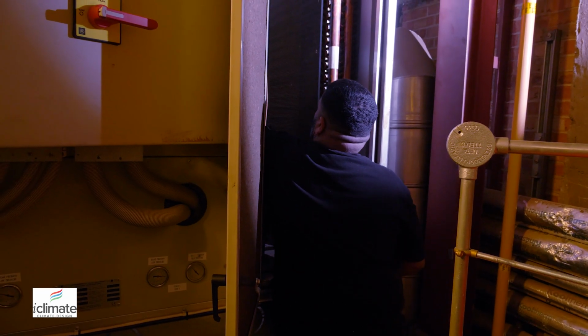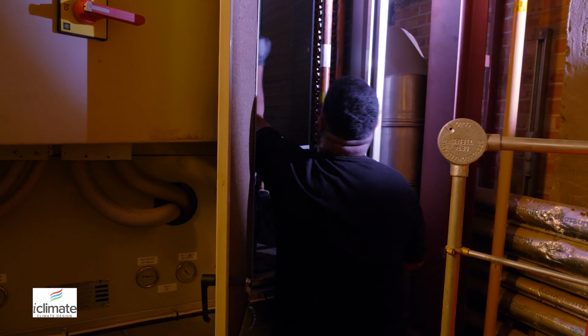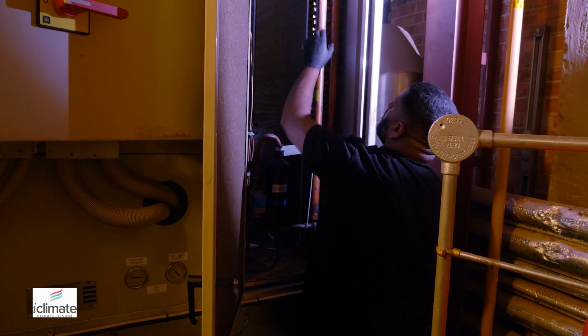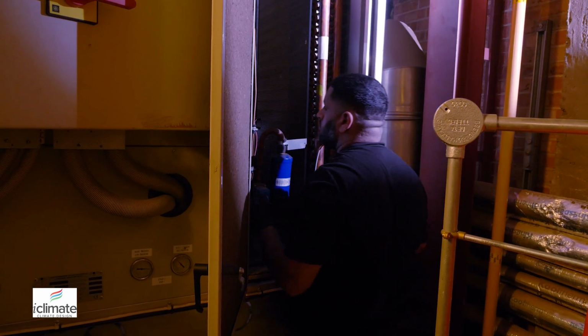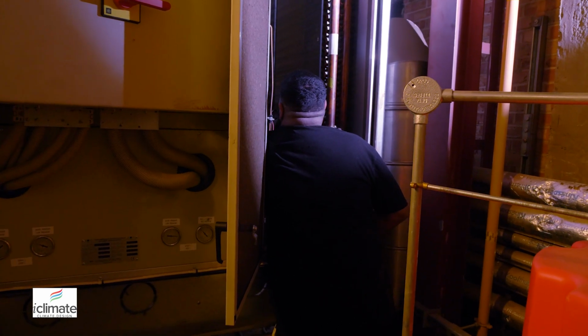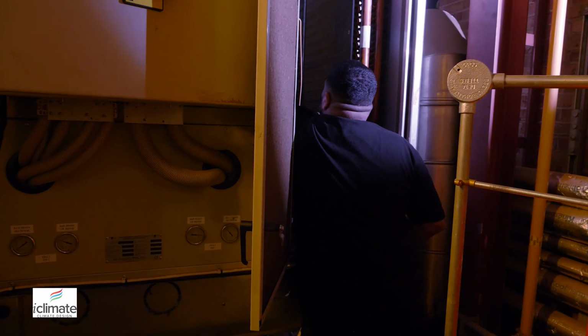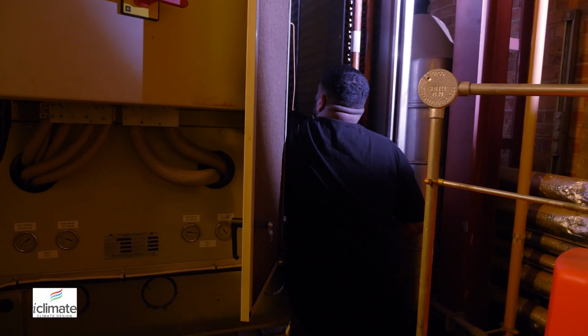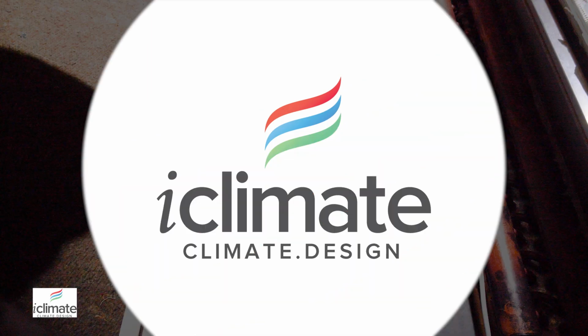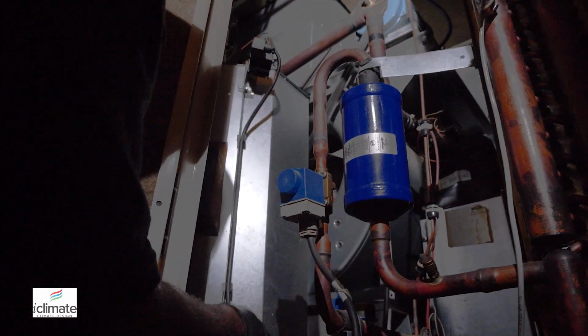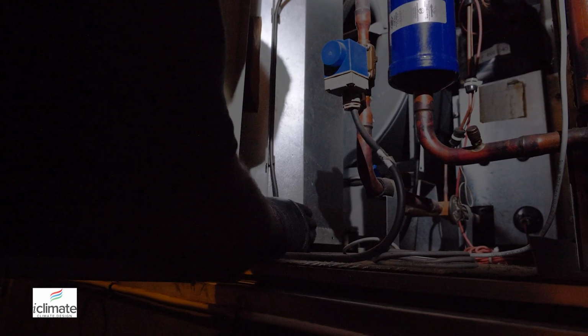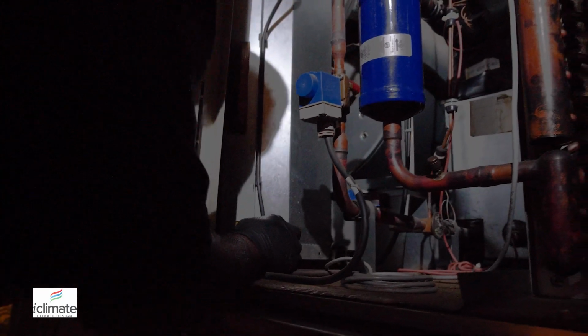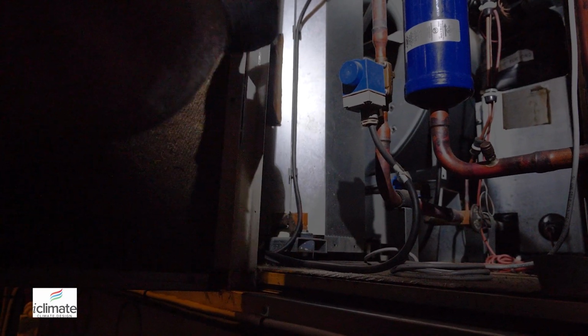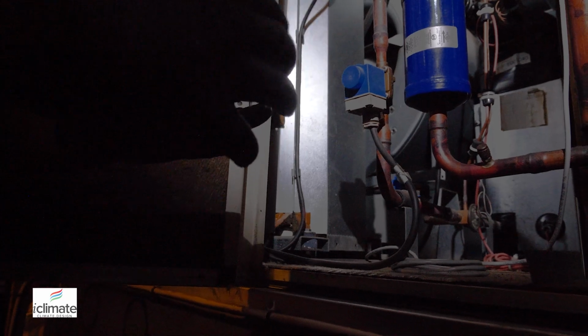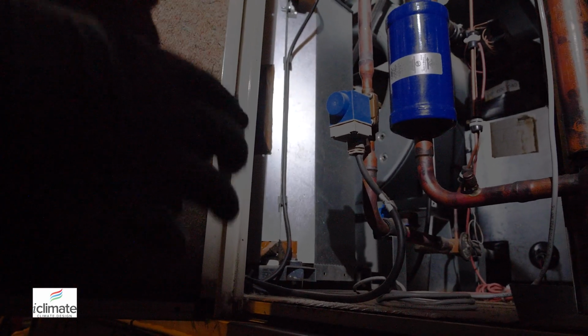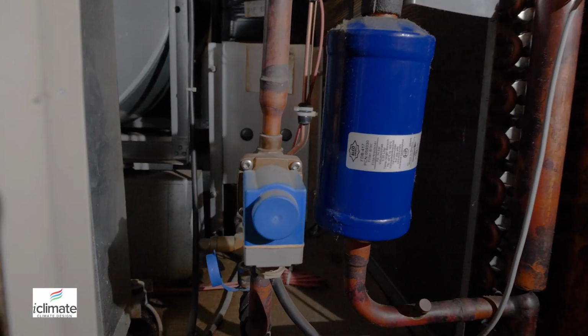But as we full well know, with systems like this that diversify, sometimes you do not get a full liquid head here because you may be only running on one compressor or one expansion valve, at low duty with a very slight opening, which would then cause the liquid line not to be at full capacity, right? And these boxes behind here are the compressors. There are two of these boxes because there are two circuits here, step 1 and step 2. And when it comes to looking at chillers, key small measurements that you would do on a smaller air conditioning system are very detrimental here.